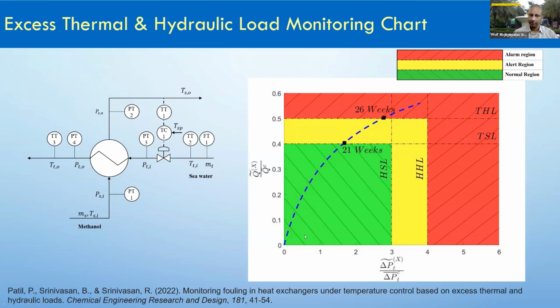In this example, a particular heat exchanger was monitored, and after 21 weeks without cleaning, they found the efficiency had dropped. It was still okay, but they should plan to clean it in the next month or so to remove the foulants. We found that if they didn't clean it for the next 5 weeks, by week 26 the efficiency had dropped so much that they were wasting a lot of energy to provide the same heating the process requires.